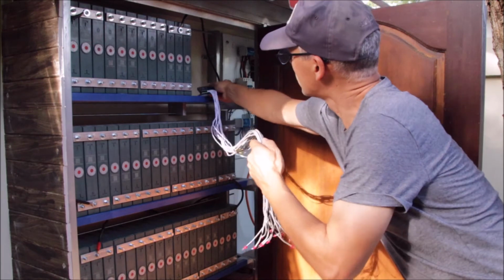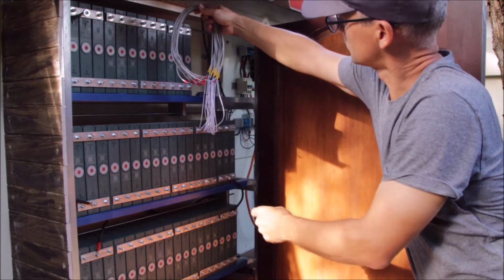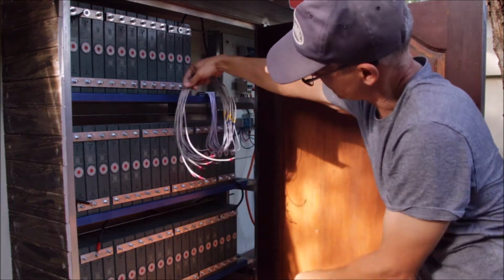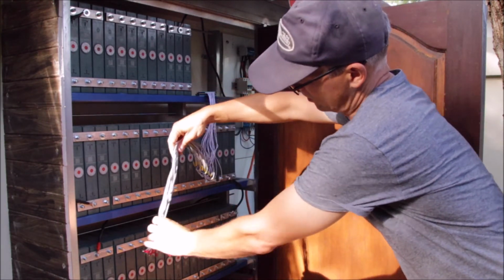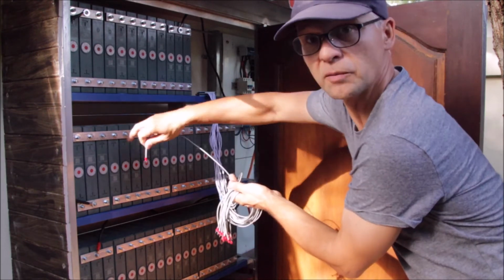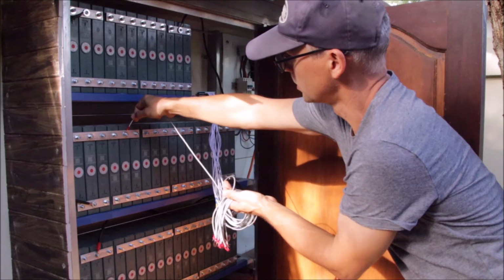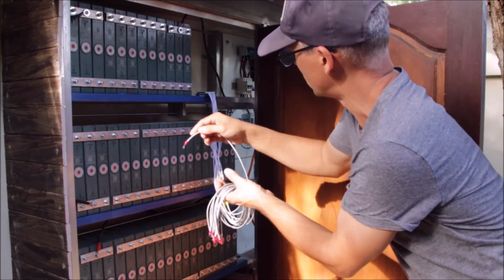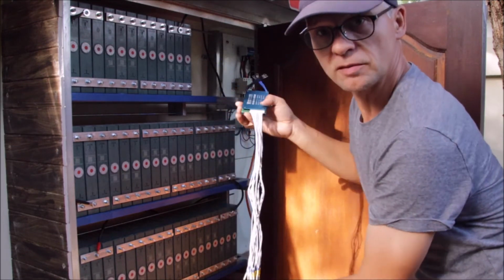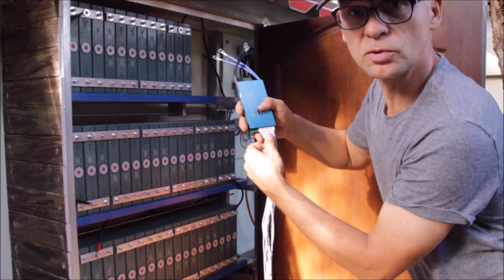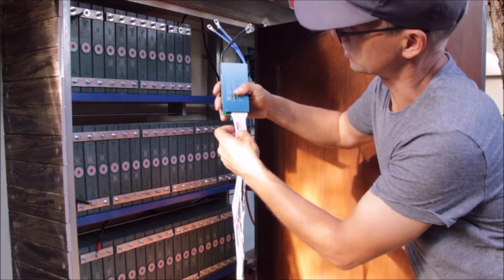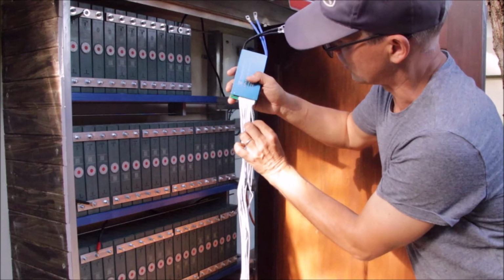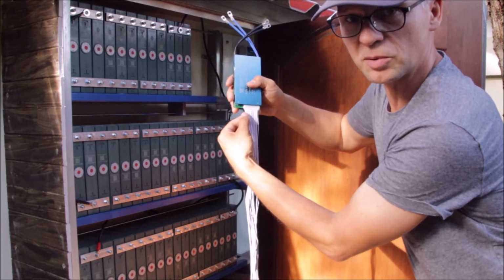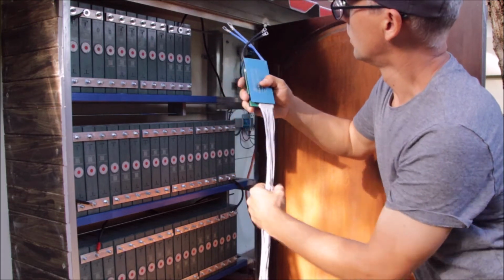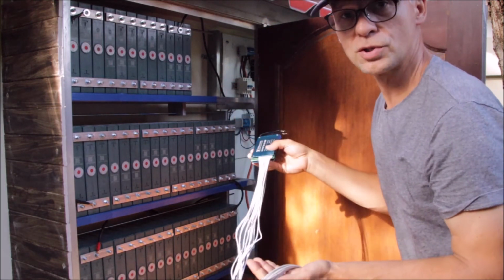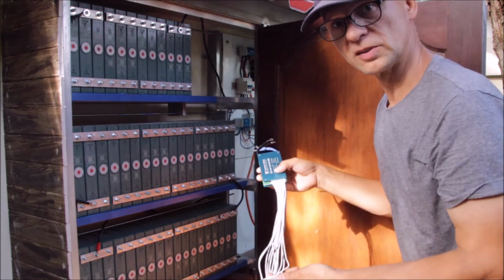The BMS will stay somewhere in this area, and then we can route all the balancing leads from the back side of the battery cells to the bus bars. We'll use one of these bolts here and add the balance lead to it. It's fairly simple, but the only thing we need to be careful about is using the correct order of these balancing leads — if you make a mistake here, that's not good. I'll do the job and show you how it looks when finished.